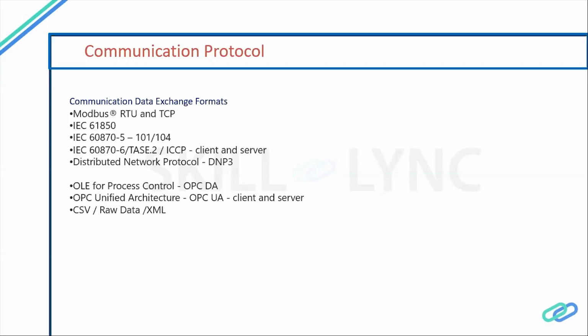So basically in SCADA we are trying to save a lot of money. During the engineering stage, if you go to a cement plant or refinery, there may be approximately 7 or 8 operating stations. For cost optimization, they take maybe 2 servers and 4 clients. Otherwise, with 8 servers, the cost is very huge. Second, you are not able to manage data for 8 servers, because across all 8 servers there is some time difference of milliseconds or microseconds. Even if you put in a GPS clock, some time difference definitely remains. So we need to interface data and sync time, and we provide only 2 SCADA servers.